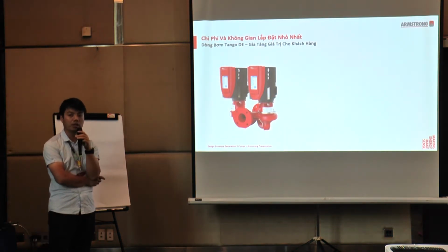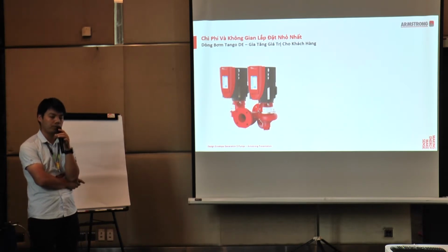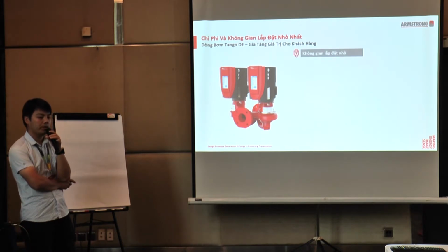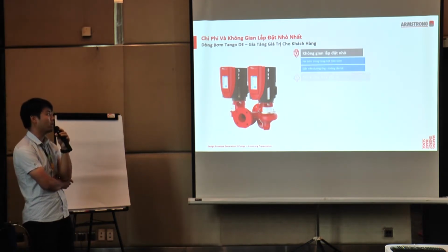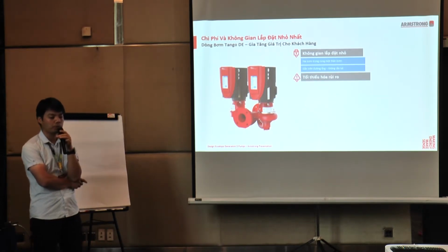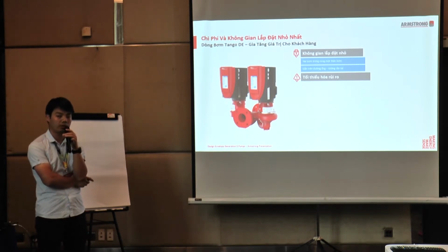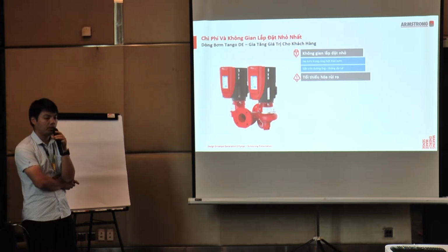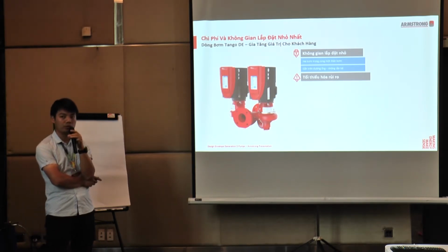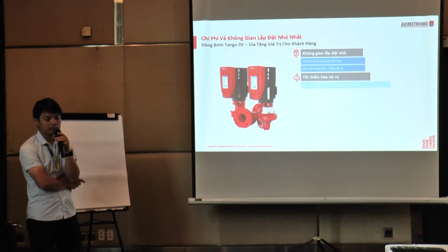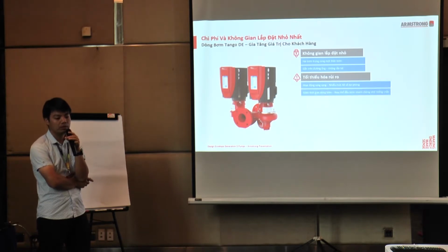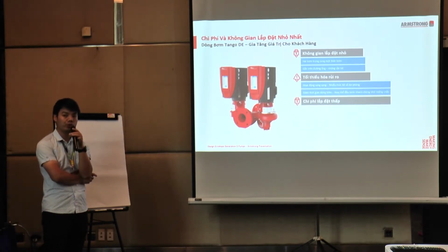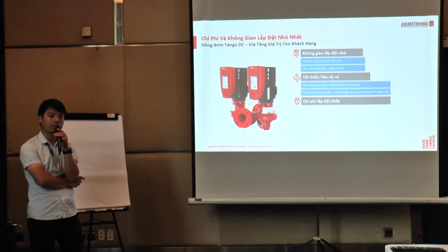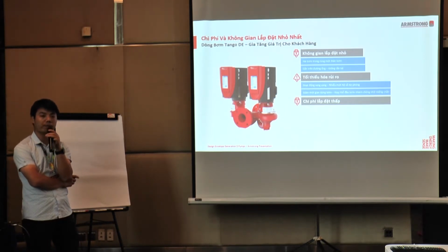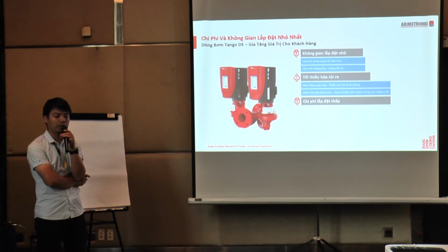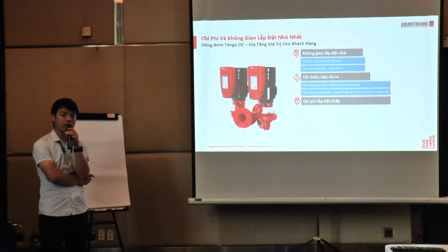Now let's look at the benefits of our new generation 5 pumps. First is low space requirements, because two pumps are in one casing. We just talked about this. The second is that it is pipe mounted. There is no base required for the Gen 5 pumps, and we can also mitigate the risk for the pumps, such as reducing the downtime. If one head of the pump fails, we can use a blanking plate to service that pump.